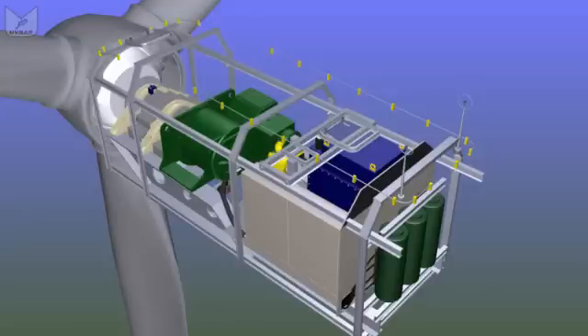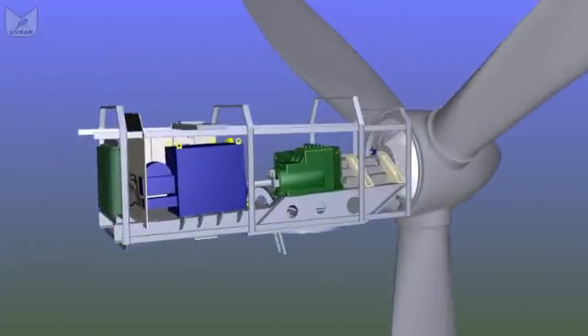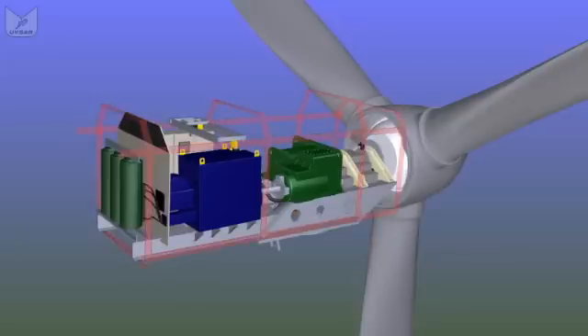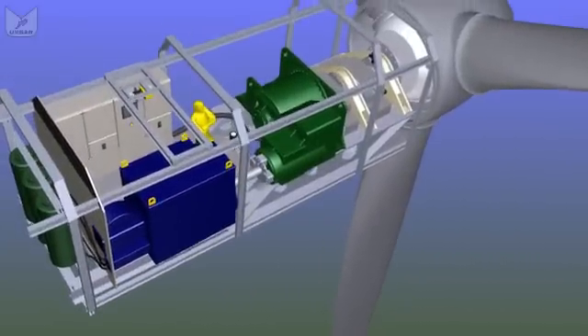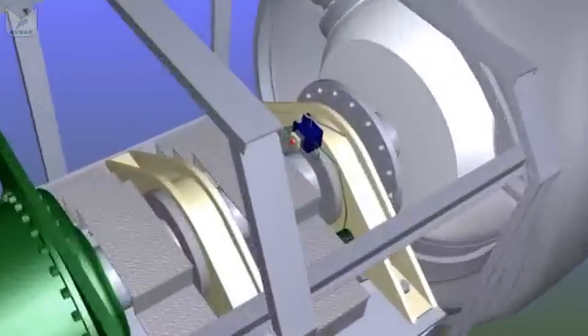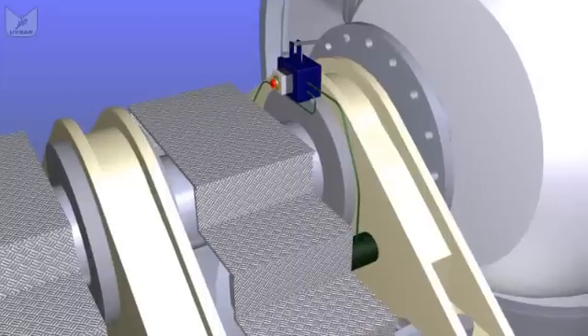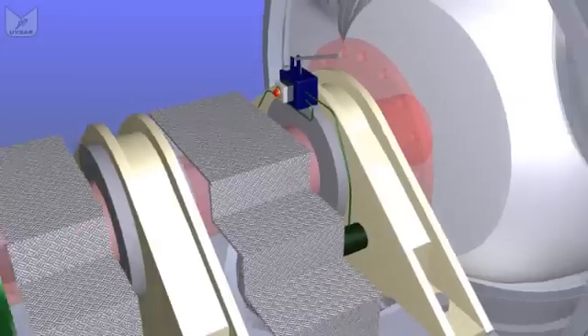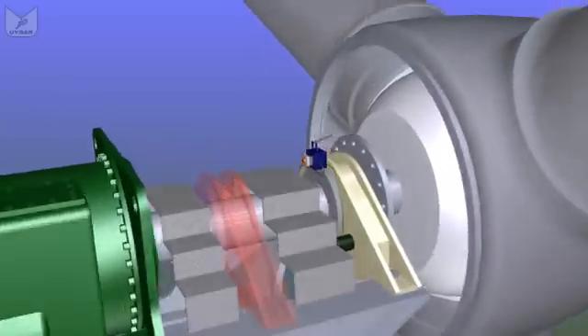If we take the skin off the box, inside we have the same kind of components we had before. They're just bigger, and there's a little bit more room, so they're laid out a bit differently. The only additional component up here is those three green cylinders at the back. That's our high voltage transformer, which used to be at the base of the tower. Now we've removed a lot of the control systems and the hydraulic systems that would just clutter up the pretty picture. We've added in a bloke for scale, but most of the big components are still here. If we look at the very front of the nacelle, we have a couple of bearings which support the main shaft, which is a hollow tube, 50, 60, 70 centimeters in diameter. It's hollow so that we can get electrical cables in through this main shaft into the hub to drive all the control systems inside the hub, and we have a couple of pins on the first bearing that lock the main rotor in position if we need to access the hub. It's a safety feature. If you're in there and it starts rotating, it gets scary.